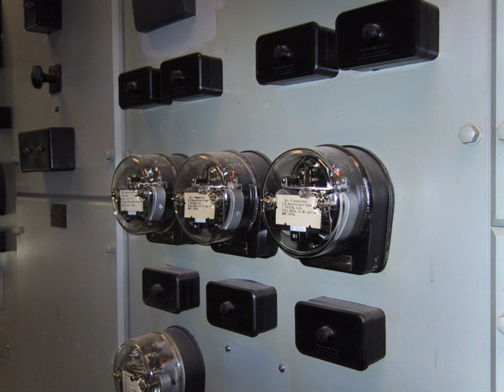Topic: Current differential protection scheme. A differential scheme acts on the difference between current entering a protected zone, which may be a bus bar, generator, transformer or other apparatus, and the current leaving that zone. A fault outside the zone gives the same fault current at the entry and exit of the zone, but faults within the zone show up as a difference in current. The differential protection is 100% selective and therefore only responds to faults within its protected zone.